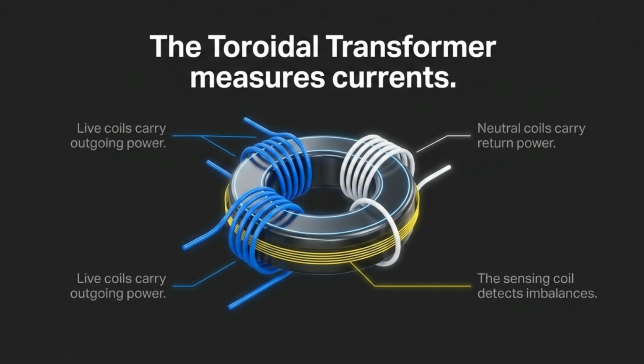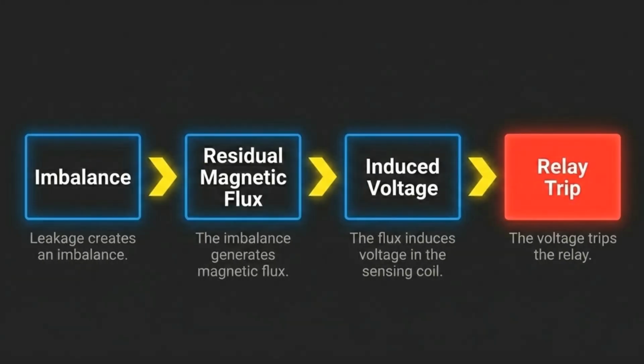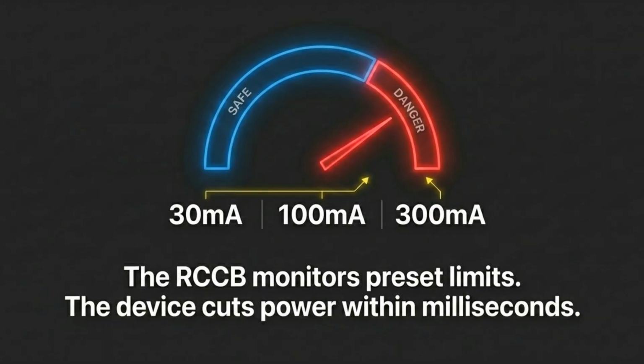The toroidal transformer is the component that measures these currents. It features live, neutral, and sensing coils. Leakage creates an imbalance, generating residual magnetic flux, which induces voltage in the sensing coil, tripping the relay. The RCCB monitors preset limits and can cut power within milliseconds when dangerous current levels are detected.